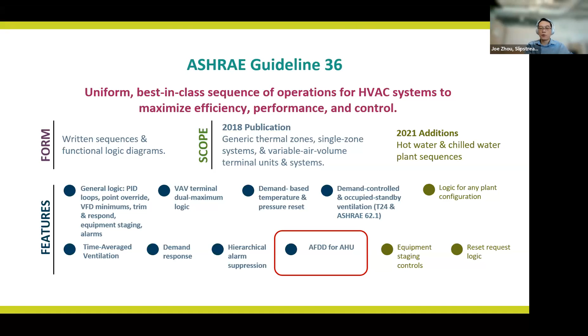This example is the duct static pressure is too low with the fan at full speed. So the equation means if you find the average duct static pressure is lower than the set point by a certain number, where epsilon DSP means a small bias range, and you cannot meet the set point while the VFD is already running at 100%, there must be something wrong. It could be a problem with the VFD, a mechanical issue with the fan, the fan design being undersized, or the set point itself being too high, so that there's too much zone demand and the fan speed is always maxed out.